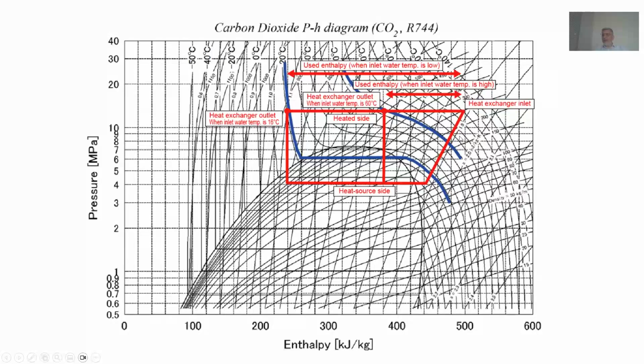So it's just a quick comparison. Again, your compressor does the work, and if your water is at a higher temperature, let's say 60 degrees centigrade, you get this much output from the system. But if your water comes in at a lower temperature of 10 degrees centigrade, you get more output from the same work done by the compressor.